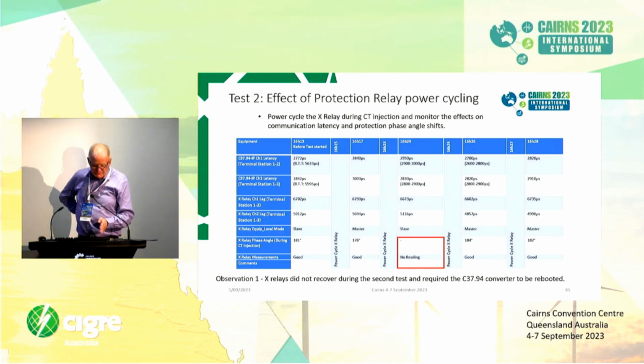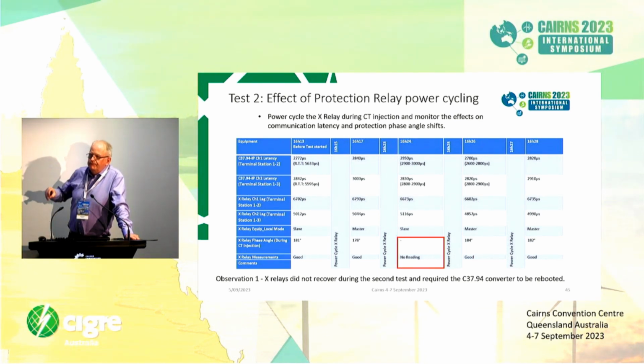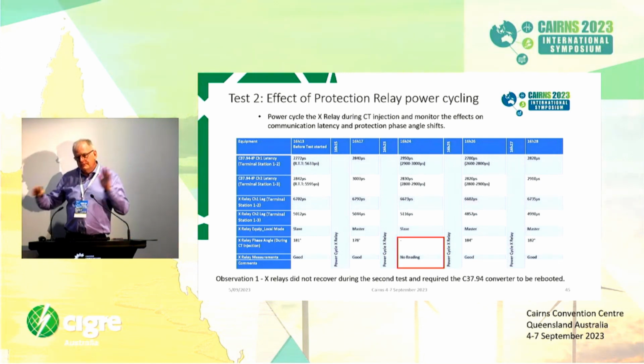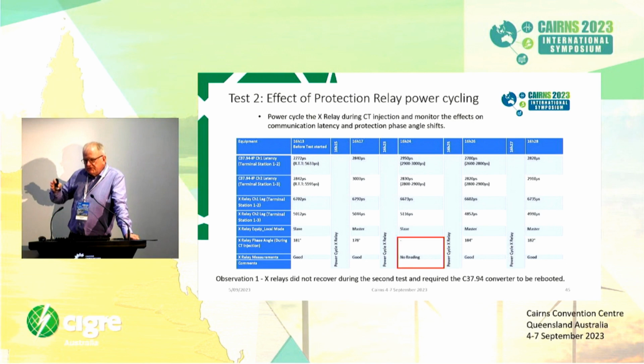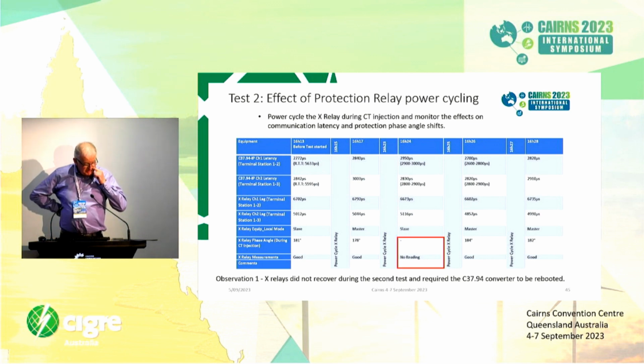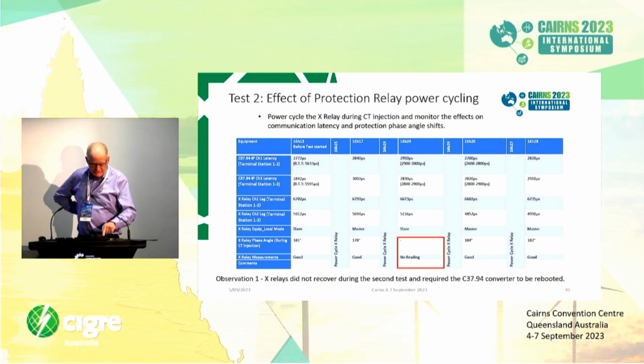So there's a slight difference there. There was 181 degrees before the test. It went to 178 degrees after the test, and you can see some slight differences there if you come to line 3 there on the relay channel 1 lag. The lag went up by about 90 microseconds, I think it is, which just indicates that it's using the ping pong method. So when the channel came back up, the relays did a ping pong time calculation, and there was some difference in the round trip time detected, and hence the latency was affected a little bit, but still within the parameters that we accept, which is that 250 microseconds that I spoke of earlier.